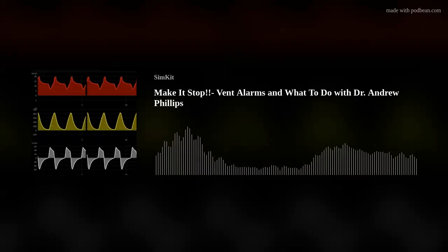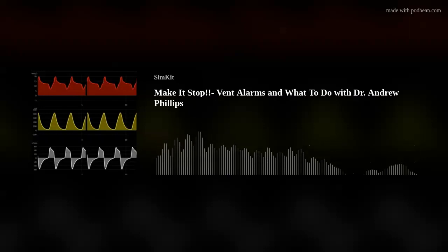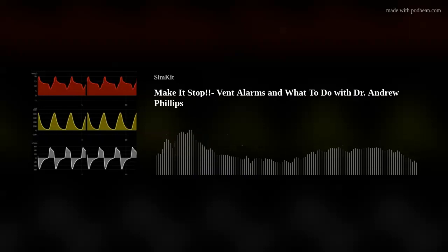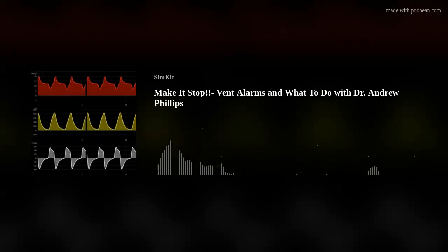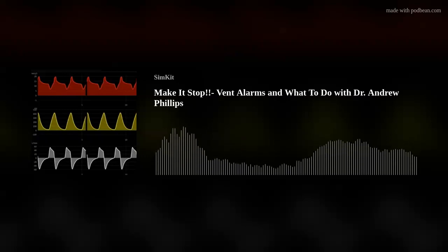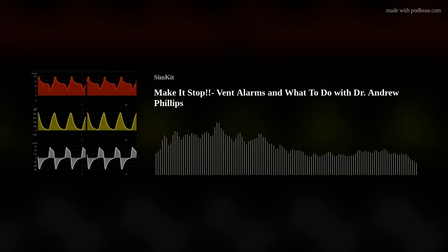So the air leak is when you have a closed circuit. This is in a secure airway, an ET tube, where it is measuring the amount of air that comes back. It gives you a sense of leak because it knows how much air went in, what the volume in was, and what the volume out was. If it's not detecting the air coming back, then it's going to alarm that there is an air leak. Air is going somewhere other than back into the ventilator, and really, that's going around the ET tube somewhere. And it means that your cuff is not working.